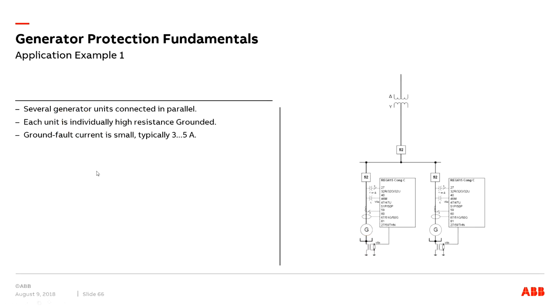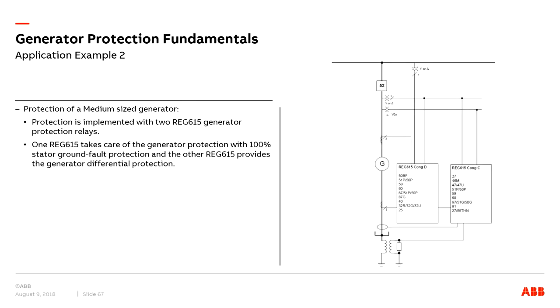This is an application example with several generators connected in parallel, where the ground fault current is typically restricted to 3 to 5 amperes. This is an example of a medium-sized generator protection, where we can use two different modules, two variants, configuration D and configuration C. One taking care of the differential, the other one taking care of the 100% stator ground fault protection.